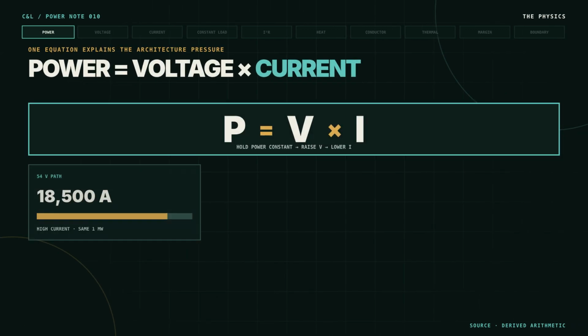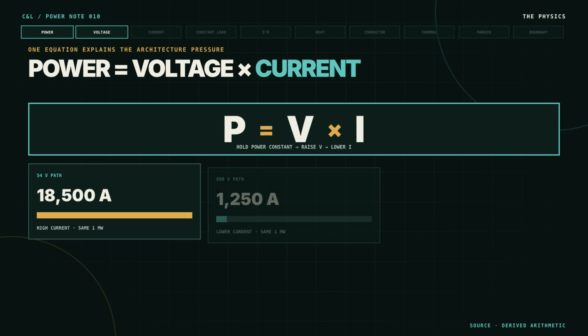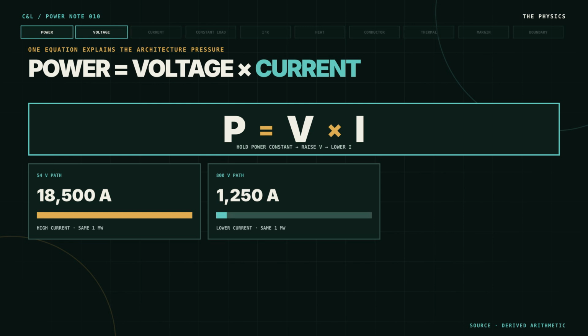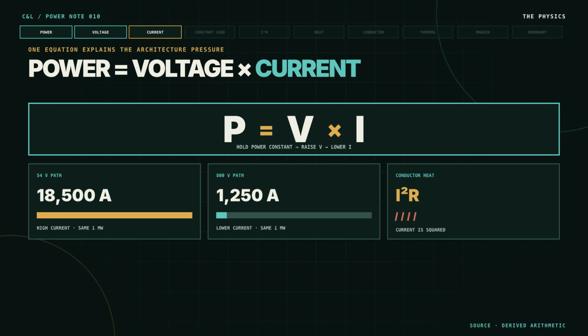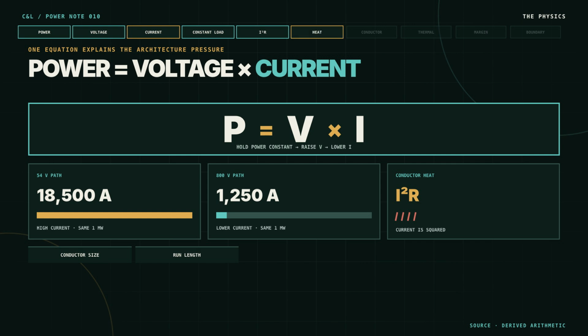Start with one equation: power equals voltage times current. Hold power constant, raise voltage, and current falls. At 1 megawatt, the ideal current is about 18,500 amps at 54 volts and 1,250 at 800 volts. This is an electrical boundary before conversion losses, not a complete product claim. Lower current matters because resistive heating follows current squared times resistance. Real designers trade that margin among conductor size, run length, thermal limits, redundancy, and efficiency.